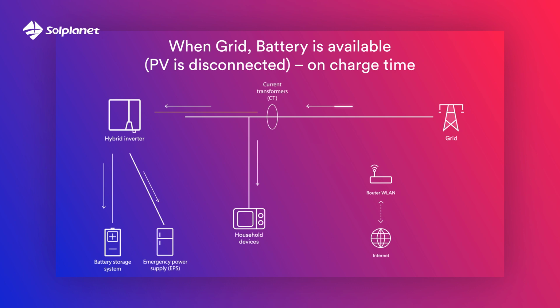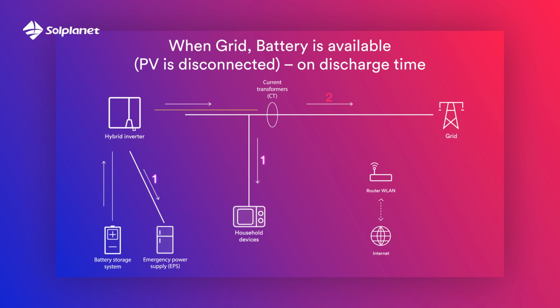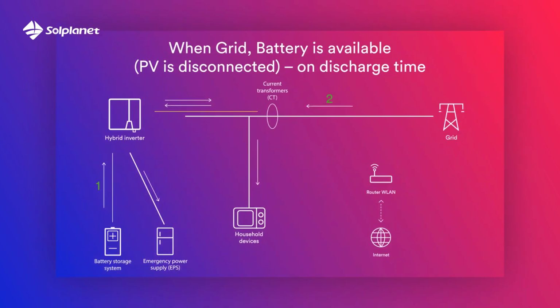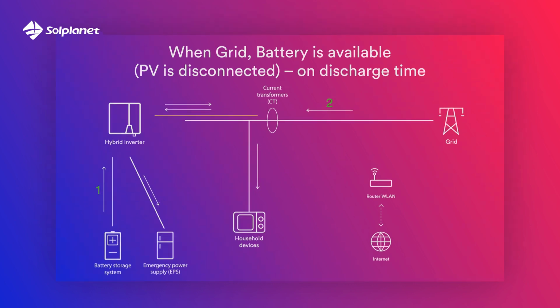On charge time, the grid will charge the battery and supply power to the connected loads at the same time. On discharge time, if load power is less than battery power, the battery will supply power to loads as first priority. The excess power will be fed to the grid. On discharge time, if load power is more than battery power, battery and grid will supply power to the loads at the same time.